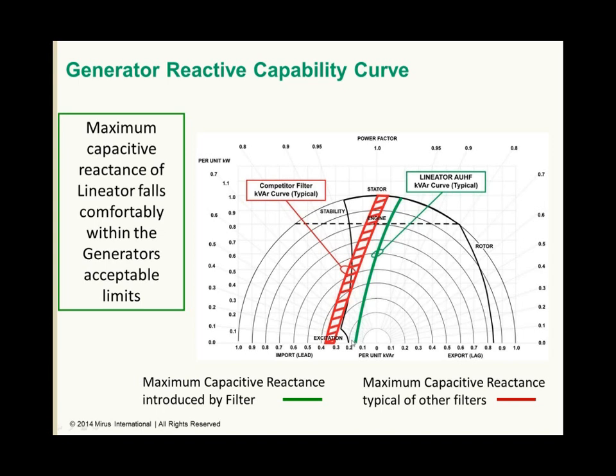But on the capacitive side or the leading side, this particular one actually can handle 20% maximum at no load. That increases a little bit as we start to load and then has a kind of an awkward curve here. But since the capacitive reactance of the filter is highest at no load, the no load requirement is the one of most concern. So we can see here other filters are outside that envelope. So if this generator was loaded with variable speed drives that were filtered with passive filters of these competitors, the generator would struggle with its excitation control, whereas the Lineator is comfortably within that envelope.